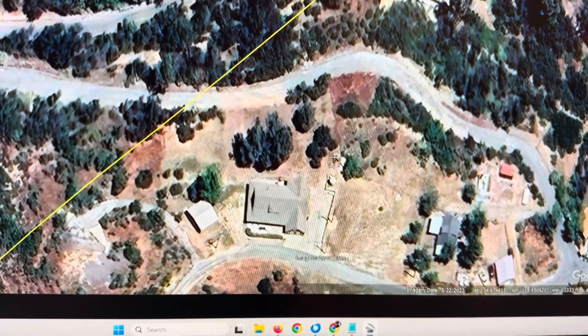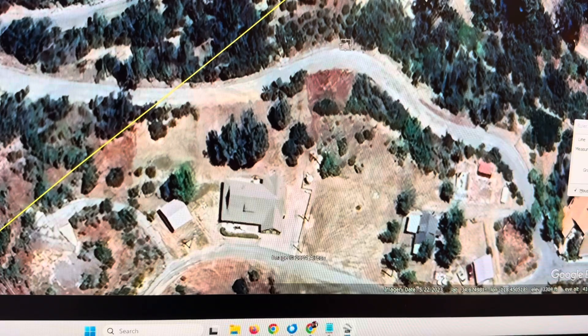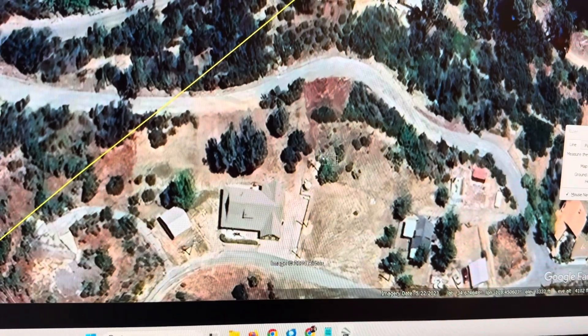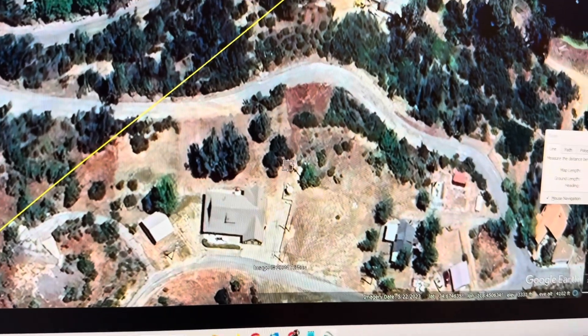Then I took the parabolic ultrasonic dish out and sure enough - west phase. The lines come up the hill this way. There are three lines: the west phase, the center, and the east phase. And the west phase lightning arrester - I was able to pinpoint that.